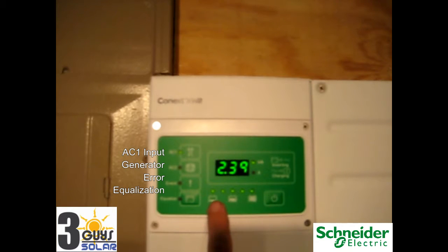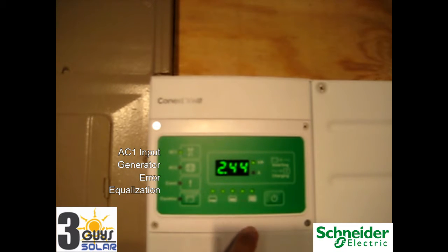Next set of lights here is our battery status light. This shows the status and the amount of available energy estimated in the battery bank. Our system currently is full when all 5 lights are on. That means the battery bank is filled, and as energy is used from the battery bank during an outage, the number of lights will turn off and go down, and you'll be able to see that the battery is losing power. At some point the inverter has a low voltage disconnect.